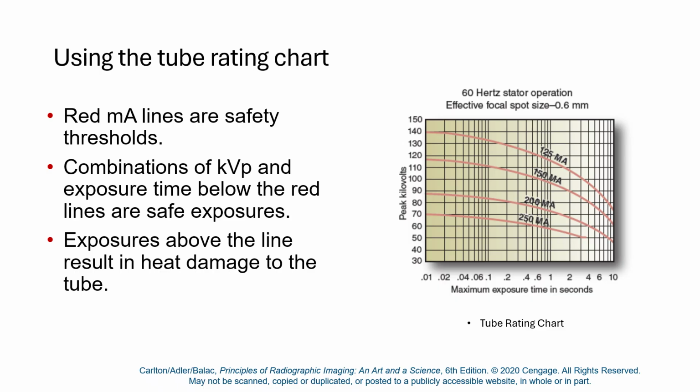You're going to damage your tube. But you can set 100 kV, 0.2 seconds exposure time and 150 MA, and you won't damage your tube. Okay.